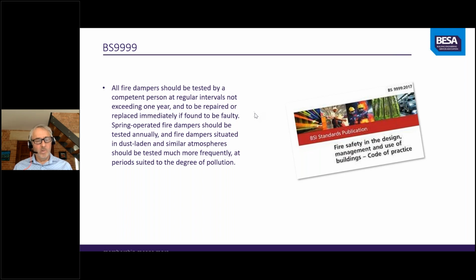So where do we stand at the moment? Well, BS 9999 says that all fire dampers should be tested by a competent person at regular intervals not exceeding 1 year, and to be repaired or replaced immediately if found to be faulty. Spring-operated fire dampers should be tested annually, and fire dampers situated in dust-laden or similar atmospheres should be tested much more frequently, at periods suited to the degree of pollution.